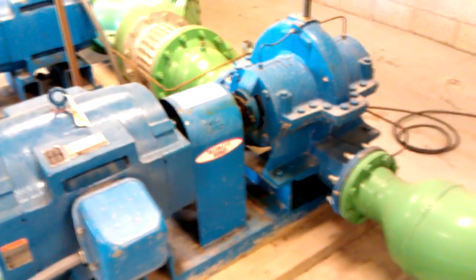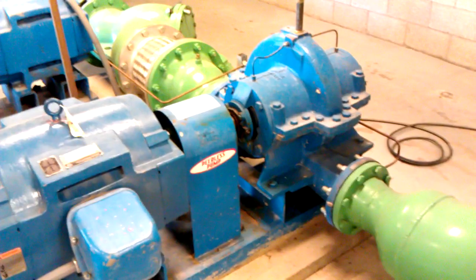I don't want the chiller to stop. So the main thing I got to make sure now is that I keep the water flowing. There is a second pump. So I'm going to open up the T up here. It basically lets it combine the chiller number 1 with chiller number 2 piping, and that way if I manually start the pump number 2, I could still cause it to flow through chiller number 1, which is what I have running. So I'm going to now close off the line to chiller number 2 that's not running.